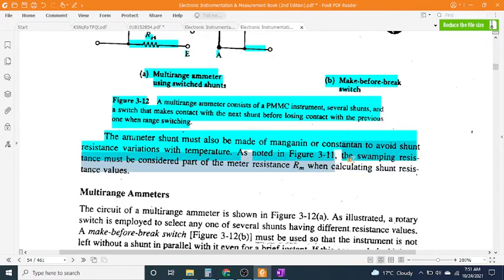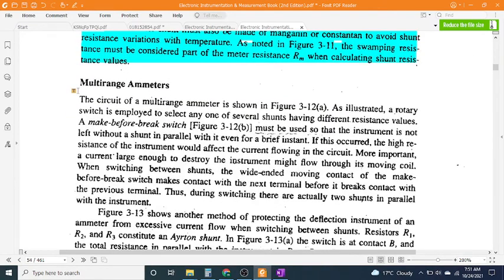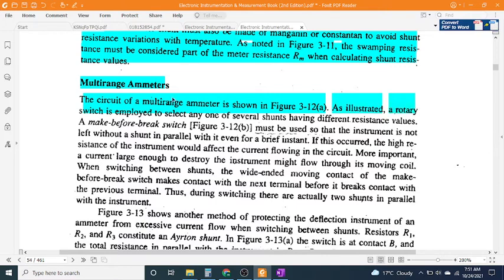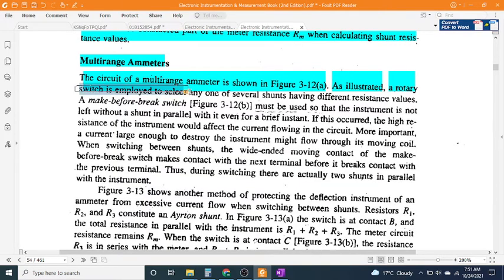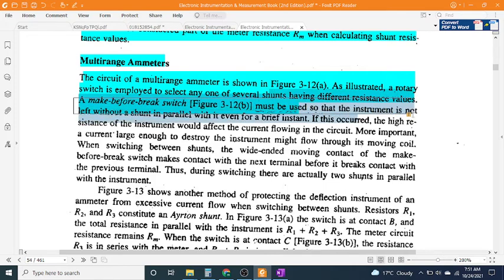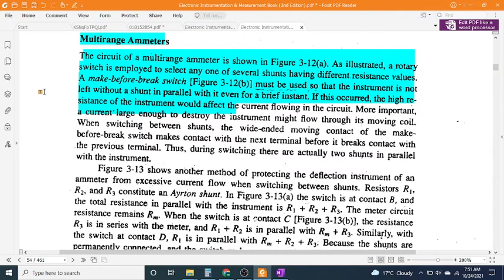Multi-range ammeter is shown in Figure 3-12A. As illustrated, a rotary switch is employed to select any one of several shunts having different resistance values. A make-before-break switch, Figure 3-12B, must be used so that the instrument is not left without a shunt in parallel with it even for a brief instant. If this occurred, the high resistance of the instrument would affect the current flowing in the circuit.